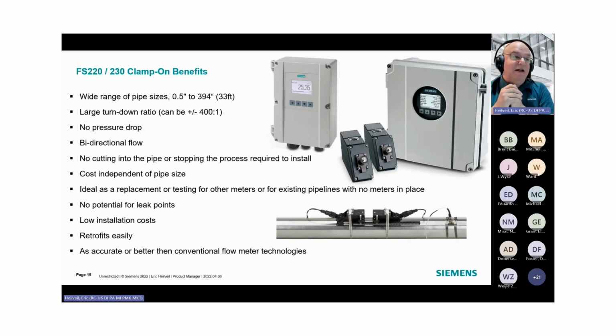So some of the cool things about this is the pricing. Once the pipe gets sufficiently large, say 15, 16, 18, 20, 24 inches and bigger, these become extremely affordable because you're only buying the transmitter and the transducers and the cables. You're not buying a huge hunk of metal. So if you bought a 20-inch pipe system and then bought a 300-inch, 350-inch system, it's the same pieces of electronics. It all looks the same. So the cost does not go up when the pipe size goes up.